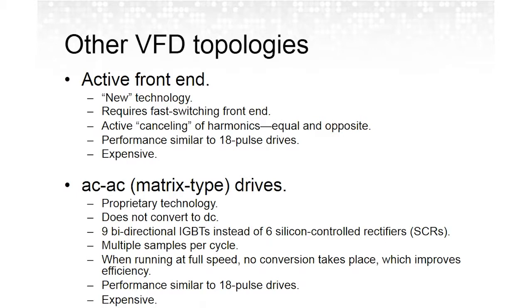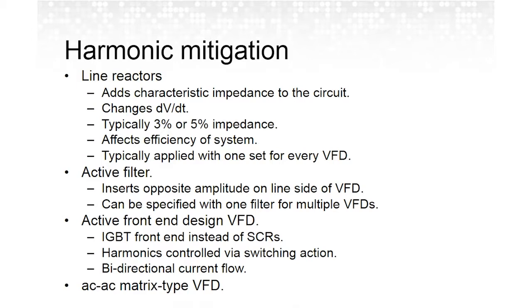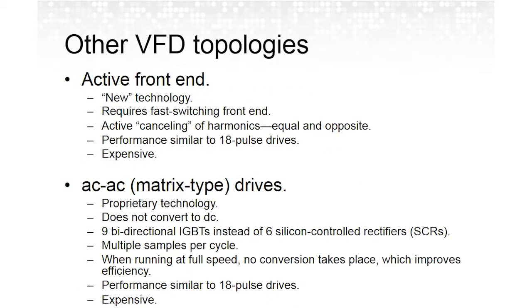So 6-pulse, 12-pulse, and 18-pulse VFDs were pretty much all that you could get for a significant amount of time, but there are other emerging technologies. They're not necessarily new. They've been highlighted in other industries, such as the data center industry for UPSs and the like, but we're only starting to see them in the VFD industry.